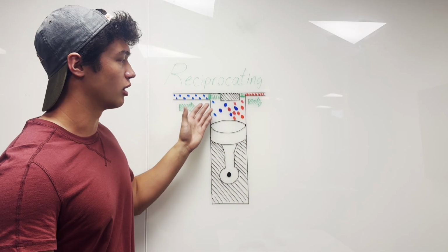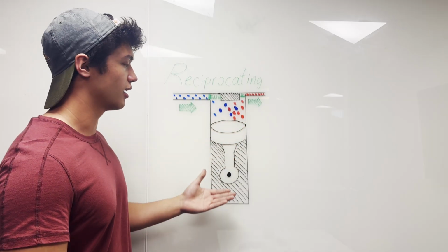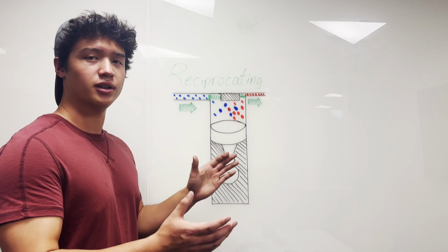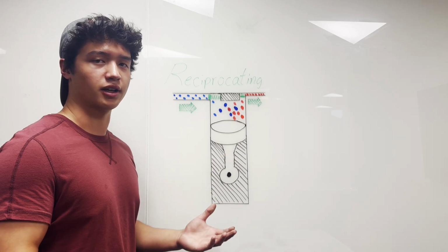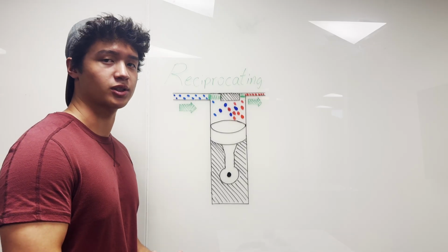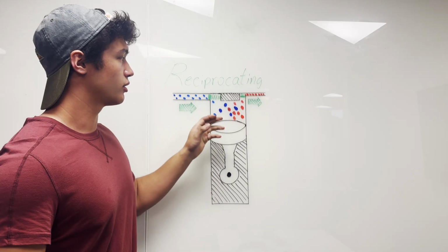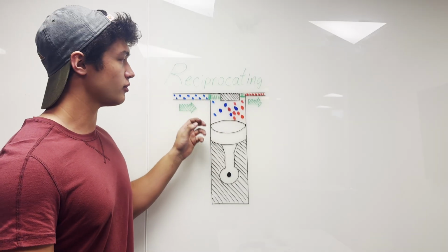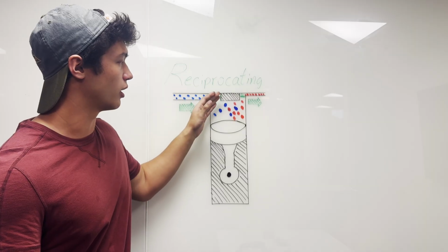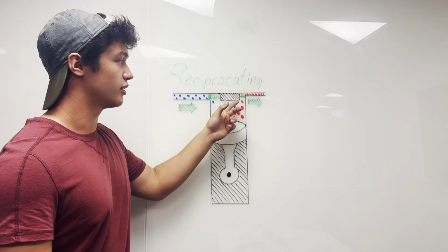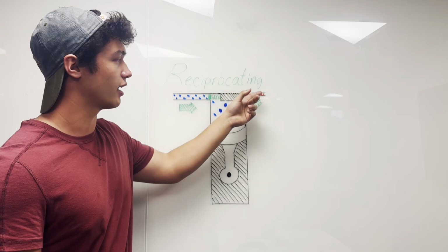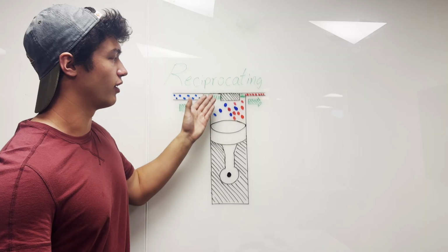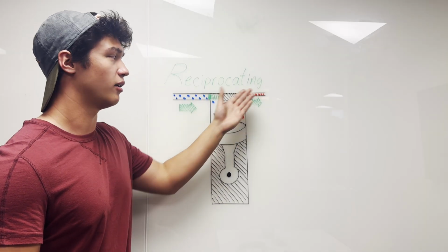It's transitioning from a low pressure to a higher pressure because, as we learned in the last video, as your volume shrinks, your pressure and your temperature rise because they're inversely proportional. So these green springs, they're symbolizing one-way valves where the vapor can go in through this way, but it can't go back out this way. And in the same way, it can go up and out, but it can't come from here back in. So then that helps ensure that we're bringing only vapor from the left side and pushing it out onto the right side.